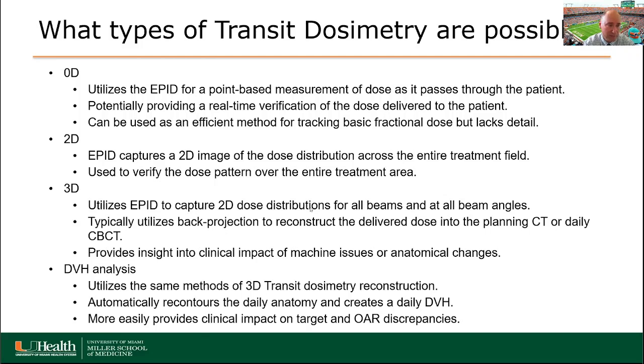3D is one step up again, where we're collecting all the two-dimensional dose distributions from all the beam angles, whether they be VMAT with rotational gantries or static IMRT. And then we use techniques to reconstruct the dose back into the patient frame of reference, either the planning CT or the daily cone. And this provides more insight into the actual clinical impact of different errors or dose distributions from changes in the patient or the treatment.